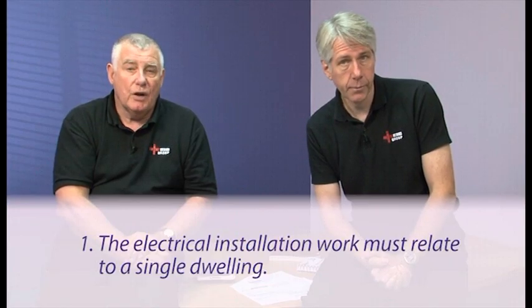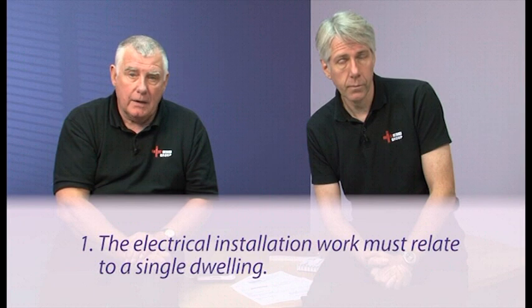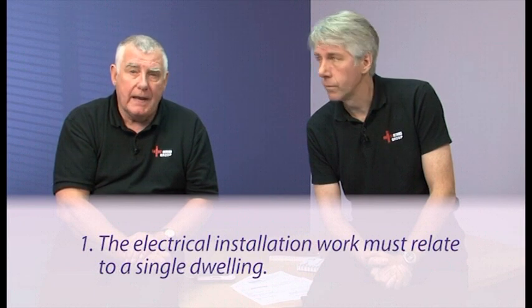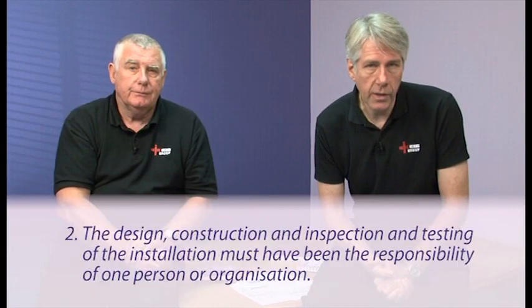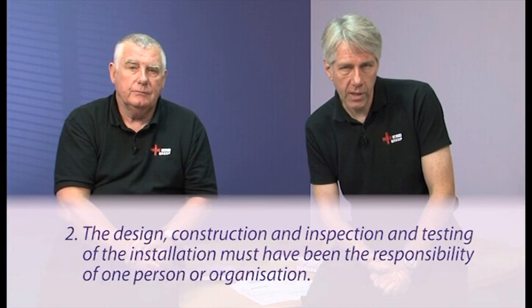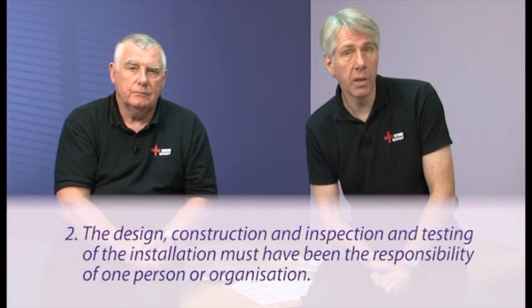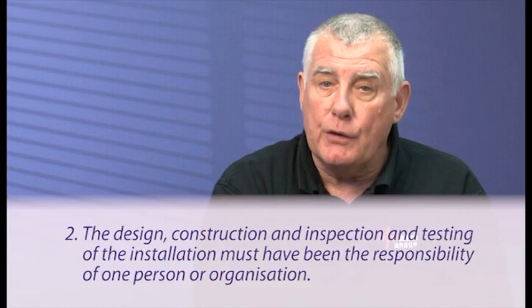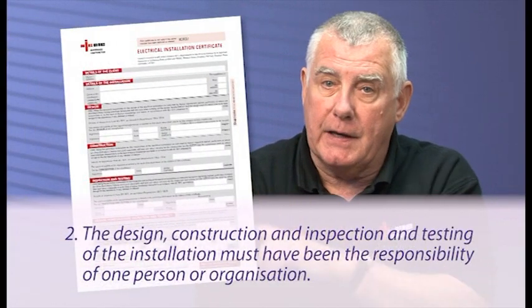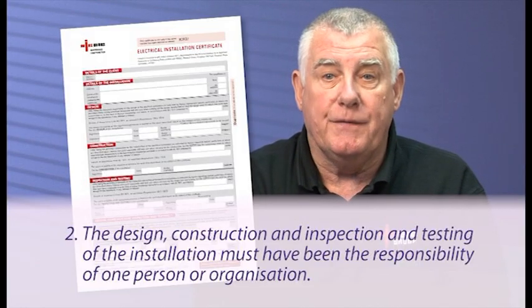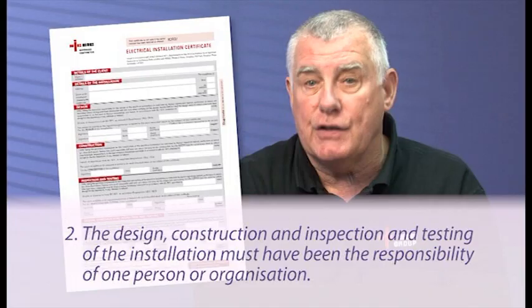If you're going to use a domestic electrical installation certificate, there are 4 conditions which must be met before it can be used. The first is that the electrical installation work relates to a single dwelling. So that's a house or an individual flat. It's not a block of flats or the landlord's supply. Secondly, that the design, the construction and the inspection and testing of the electrical installation work has been the responsibility of one person or organisation. If it isn't the responsibility of one person or organisation, then our full electrical installation certificate will have to be used, which provides boxes for each relevant person to sign.